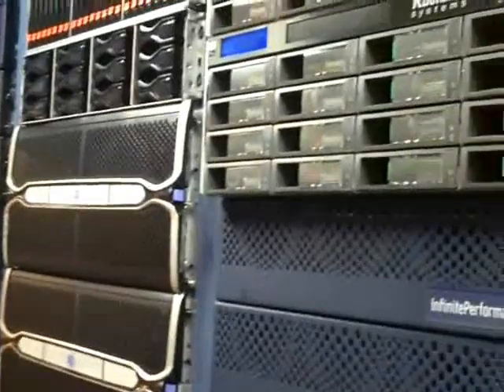So I'm going to go in here and talk about the fan and the cooling system a little bit. What you have in here is four high efficiency variable speed fans. One of the nice things we've done with the design is that the IT is on this side and the mechanical electrical is on this side. So it separates out the recurring maintenance that has to happen, where the IT guys can work on their systems. And the production unit actually has a much wider cold aisle and a much wider hot aisle, and a central hot aisle that runs the full length of whatever unit you purchased.